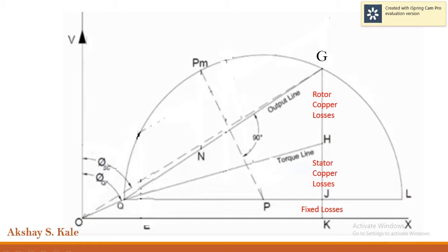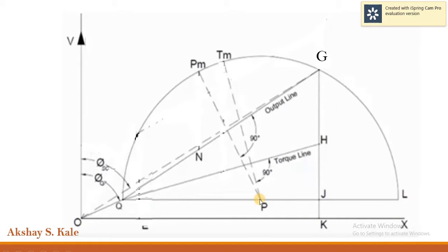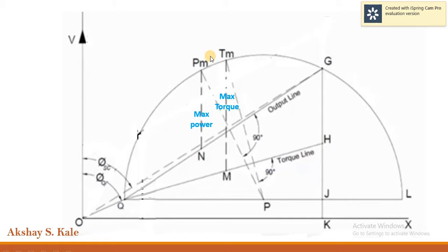From point P, draw a line perpendicular to the torque line and extend it until it intersects the semicircle at point TM. You now have three points on the semicircle: PM, TM, and G. Draw a perpendicular line to the reference line from PM up to the output line — the line between N and PM gives you the maximum power line. Similarly, draw a perpendicular line to the reference line from TM up to the torque line — the line between M and TM is your maximum torque line.